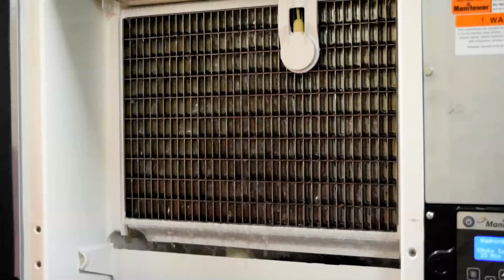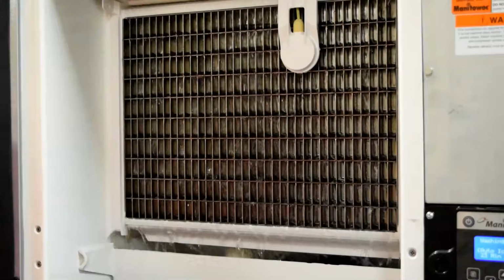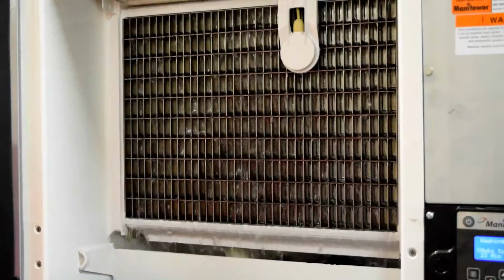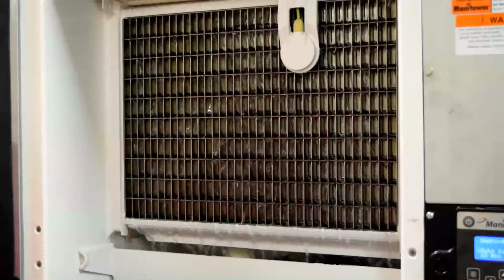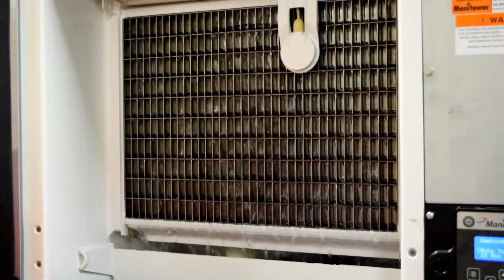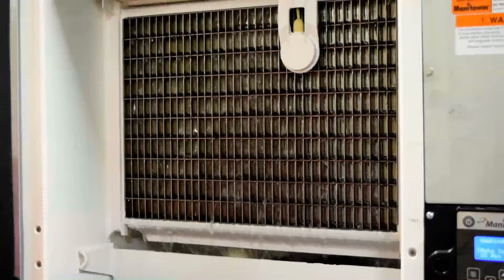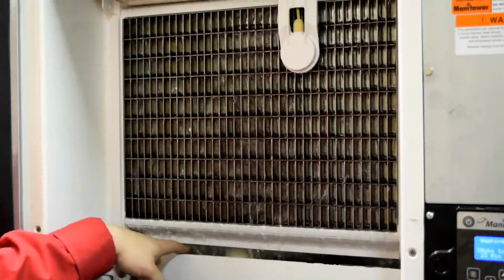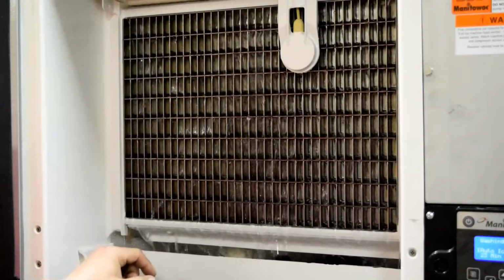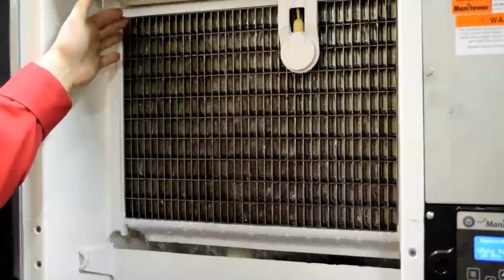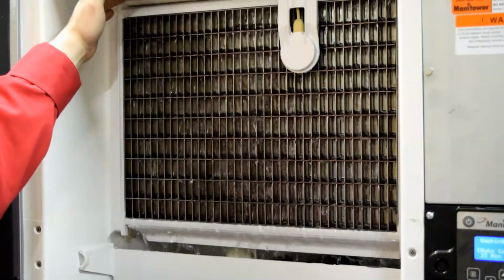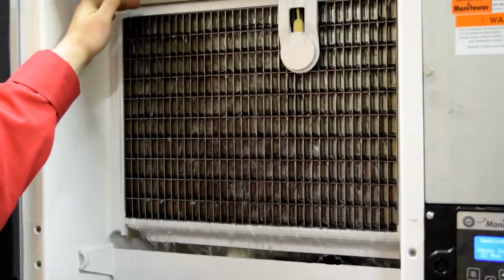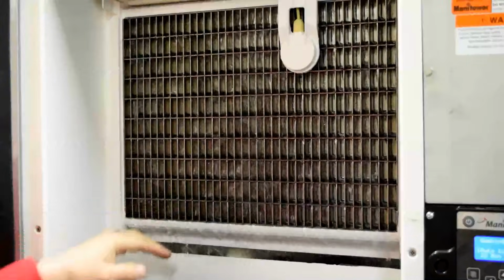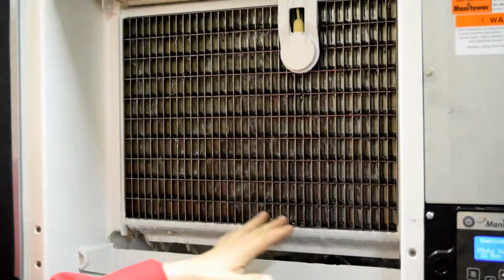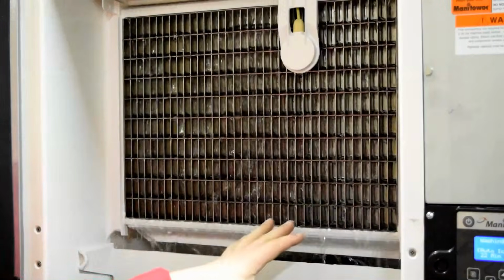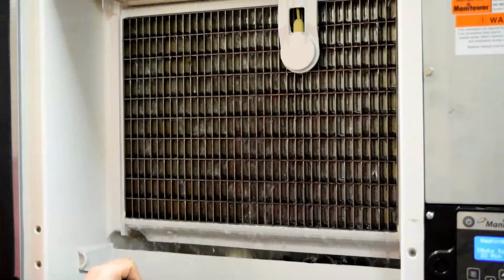I've removed the water curtain so that we may understand what is going on during the ice machine cleaning process. Remember that we added ice machine cleaner behind the water curtain. So what happens is the ice machine cleaner filters down here into the water trough. The water pump behind there picks it up, moves it up, and then the water and the ice machine cleaner solution fall down over the evaporator, so that any microorganisms that have collected here in the evaporator will get cleaned.